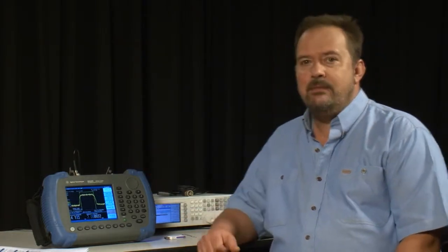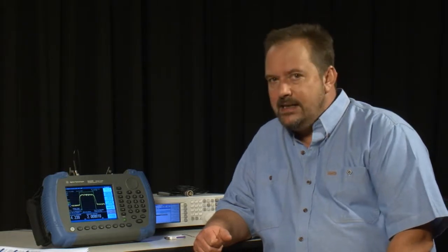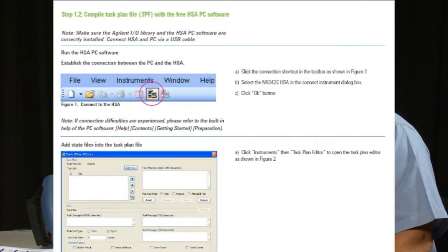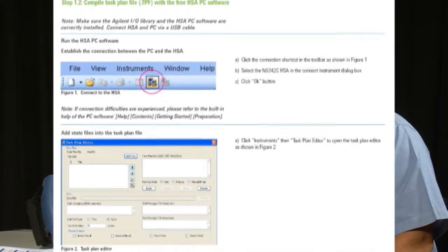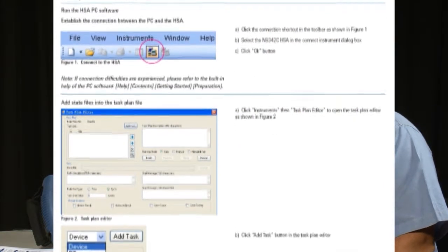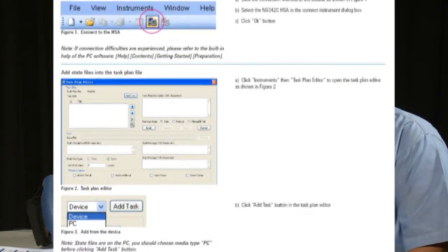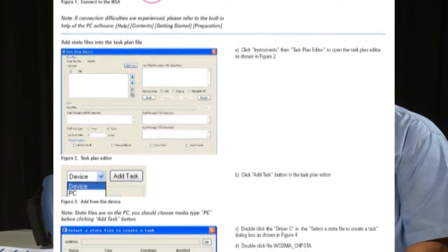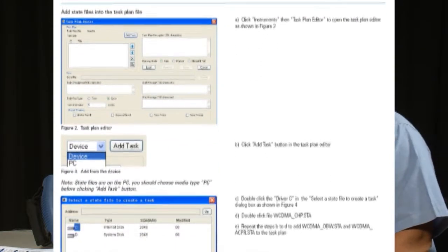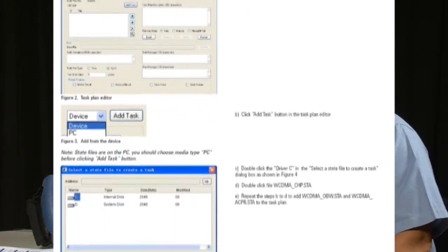The new Option TPN Task Planner capability of the N9342C allows us to do exactly that by stepping the operator through a series of up to 20 tests and automatically saving the measurement results of each test into the instrument's internal memory without needing a PC out on site.